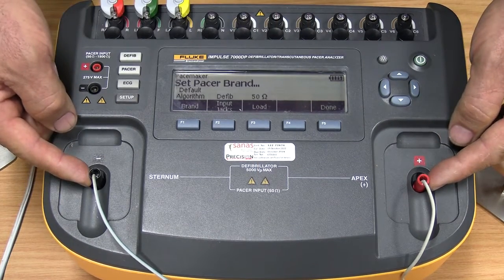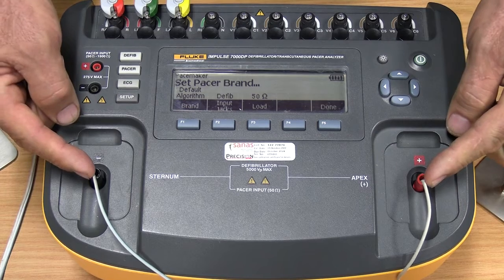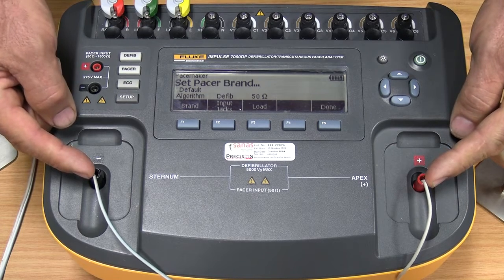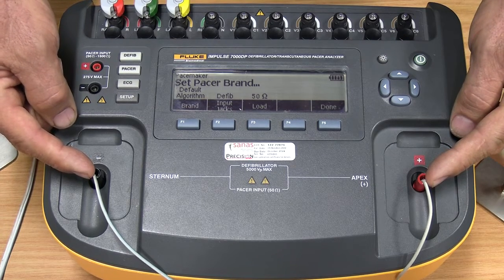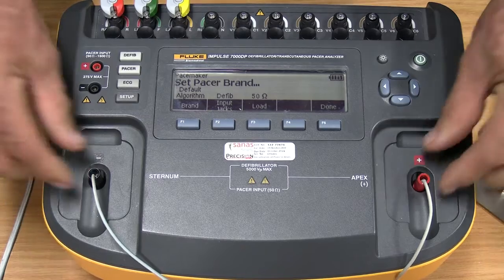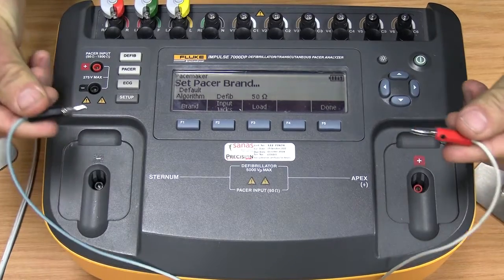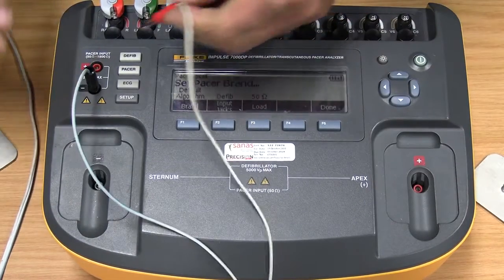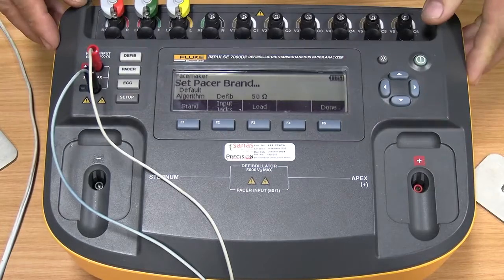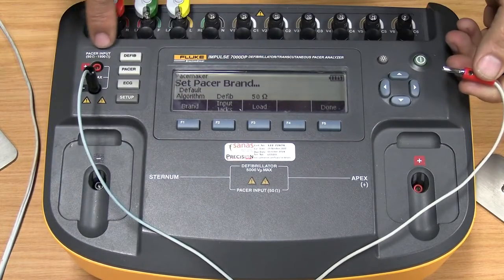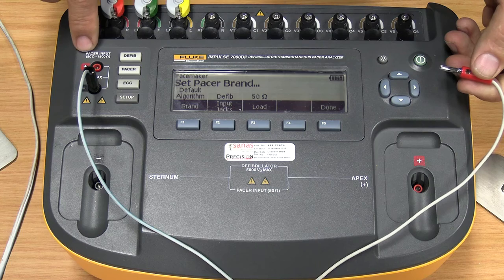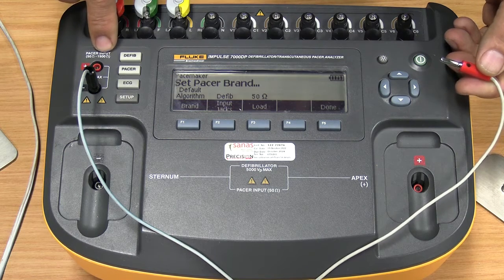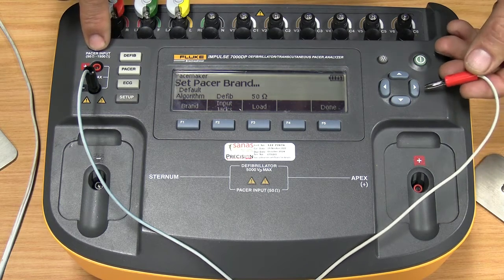If your service manual requires you to do an adjustable load, maybe do a load at 50 and at 100 and 150 ohms, we will then have to remove these two and move them to the side here to these pacer inputs. As you can see here, if I just remove this, here you have an adjustable pacer input from 50 to 1500 ohms, which you can adjust. Okay, so let's put it in there for now.